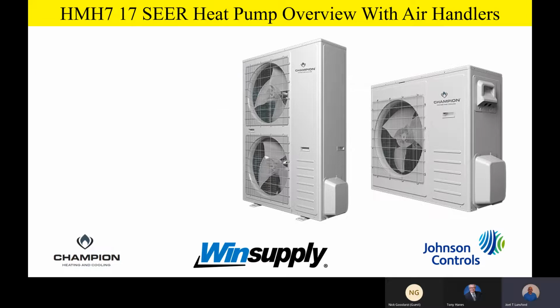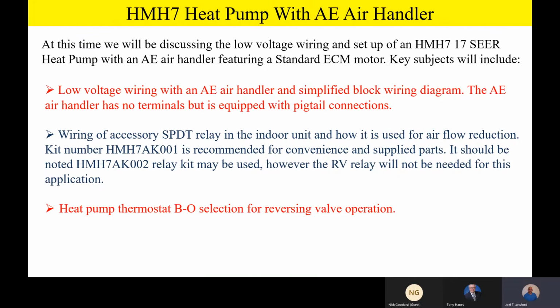Okay, well, at this time, fellas, let's go ahead and jump into the heat pump with the AE air handler. Now, one of the things we're going to be stressing today, we're going to be talking about the application of this product with the AE and the variable speed air handler only product. And we're going to have some simplified block wiring diagrams we're going to be talking about and going over. Now, we're going to recommend that on the AE air handler that we utilize that kit number HMH7AK001 for convenience and the supplied parts. Now, it should be noted, in a pinch, if you've got the 002 relay kit, you can still use that kit. However, the RV relay will not be needed for this particular application.